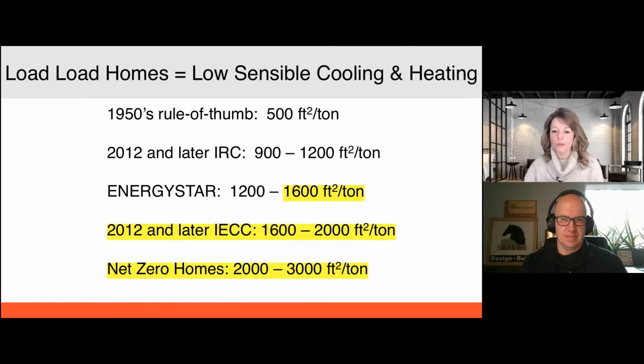But this is really what we're looking at when we start getting into our tighter homes, and that is about 1,600 square feet per ton. I think the low load homes is at 1,500 square feet per ton is what they're using in theirs. But that's virtually unheard of in the 80s and 90s, and a lot of people can't even imagine it. But the reality is if we get that air sealing right, and we get that insulation, that's what we're hoping to achieve, where we're not putting these big systems in, we're putting in smaller systems because we're not getting the temperature differences in the house like we used to anymore.